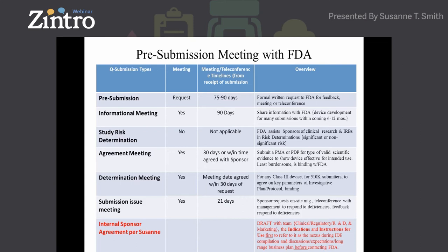Typically, keep the meeting team as small as possible — usually the president, VP of clinical regulatory, or a director, maybe one engineer or someone who knows the device and can explain it. I suggest bringing the device with you for a show-and-tell with FDA if possible. If not, bring good images so they can get engaged and understand what you're trying to achieve.